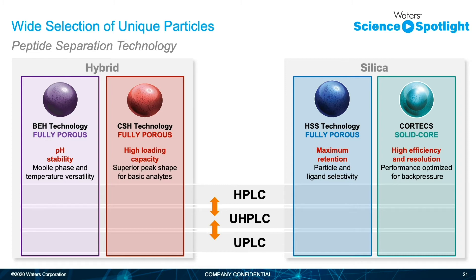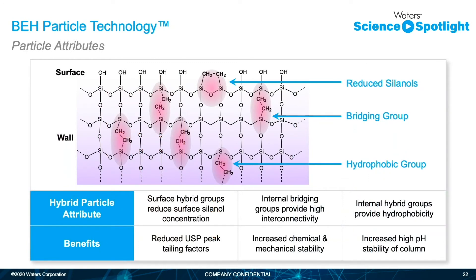The first three of the four particles — excluding CORTECS — are available as peptide columns, meaning the particles are QC'd with digested protein samples instead of a mixture of small molecules. So before you even take these columns out of the box, they have already been introduced to a similar mixture of digested peptides that you would be injecting for your peptide map or MAM. BEH technology allows for reduced peak tailing, increased chemical stability, and a much wider pH range that allows for longer column lifetimes, reproducibility, and stability. For peptides, the BEH particle is available in 130 angstrom pore and 300 angstrom pore for larger peptides or even smaller proteins.